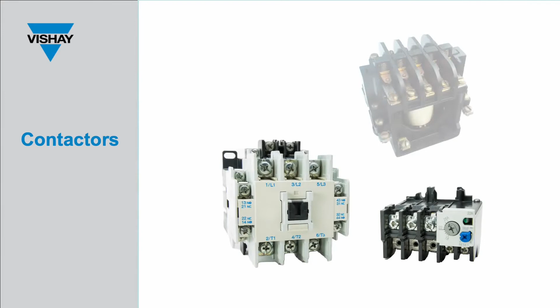Just a little bit more detail on the contactors I mentioned in the previous slide. These are conventional electromechanical devices that are basically a high-power version of standard low-voltage relays. They typically do not provide overcurrent protection, so standard non-resettable fuses are used in conjunction with the contactors to disconnect the load from the battery in the event of a fault or short circuit. Since these contactors are mechanical devices, they have a limited lifetime compared to a solid-state solution, and they also tend to be large and expensive.